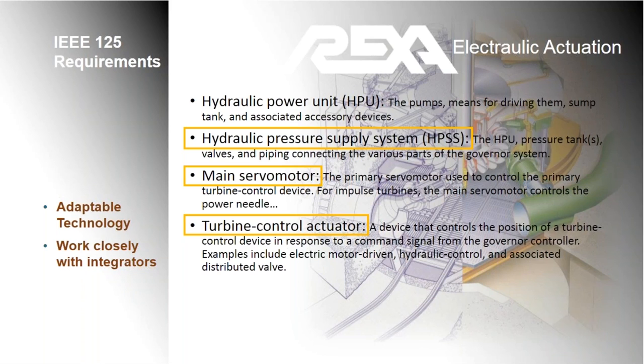Should the need for governor controls be required, we will work closely with the integrator to provide the right solution for the plant. The standard control configuration for the REXA is an analog 4 to 20 milliamp signal for set point change, and it also sends a 4 to 20 milliamp feedback signal to your control system. Other optional configurations include pulse, HART, Foundation Fieldbus, and Modbus.